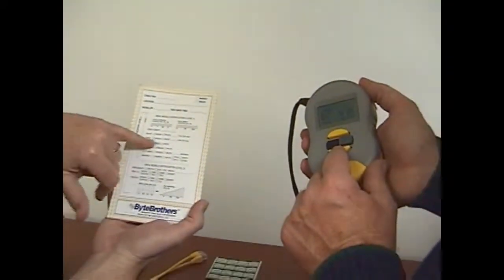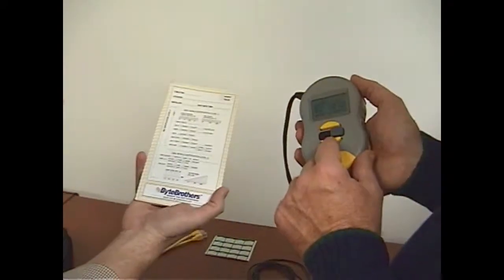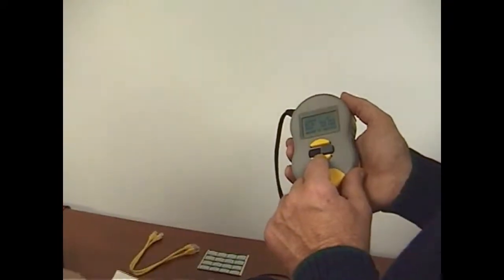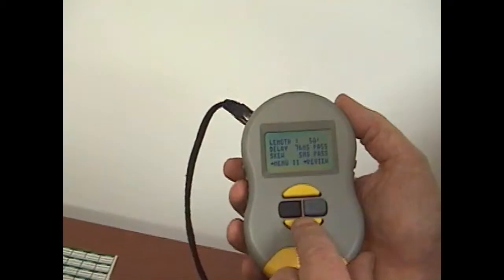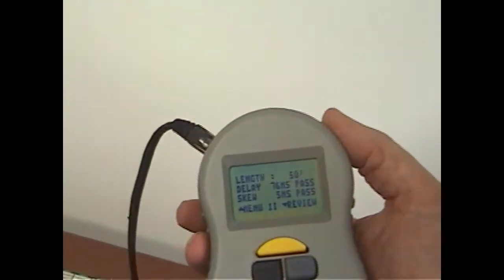The skew is 5 nanoseconds, and the standard allows for 50, so right away we sense we have a good cable. If we were out of spec, the meter would have immediately flagged the error.